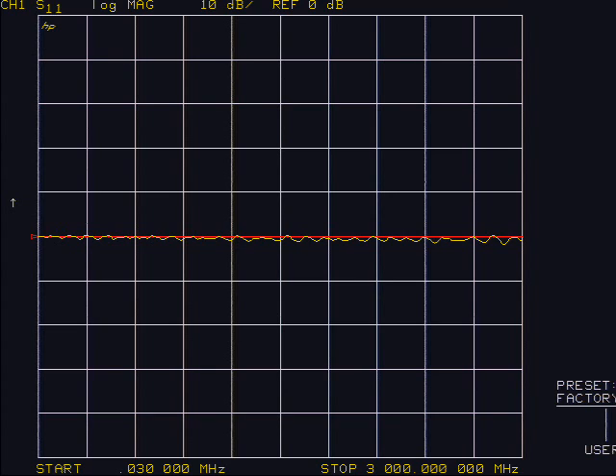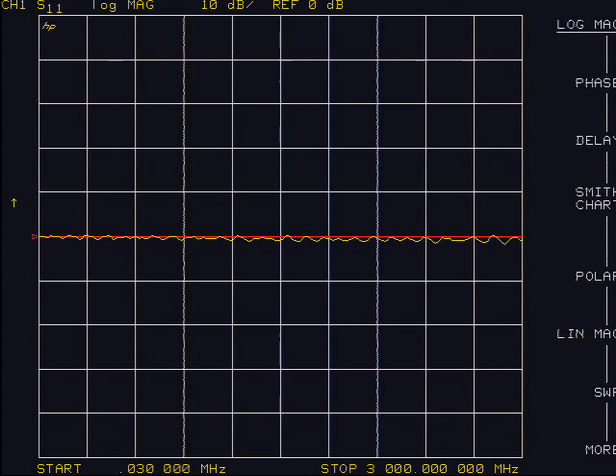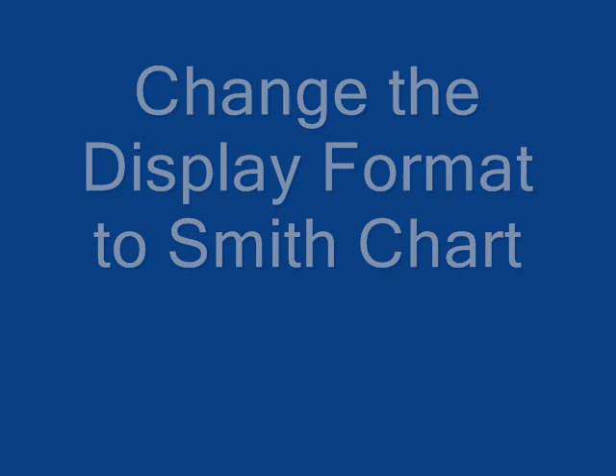Change to Smith chart display for impedance measurements by selecting the format button. The right-hand menu items on the screen are selected by keys just to their right, referred to as soft keys as they change with every button. Select the Smith chart soft key.